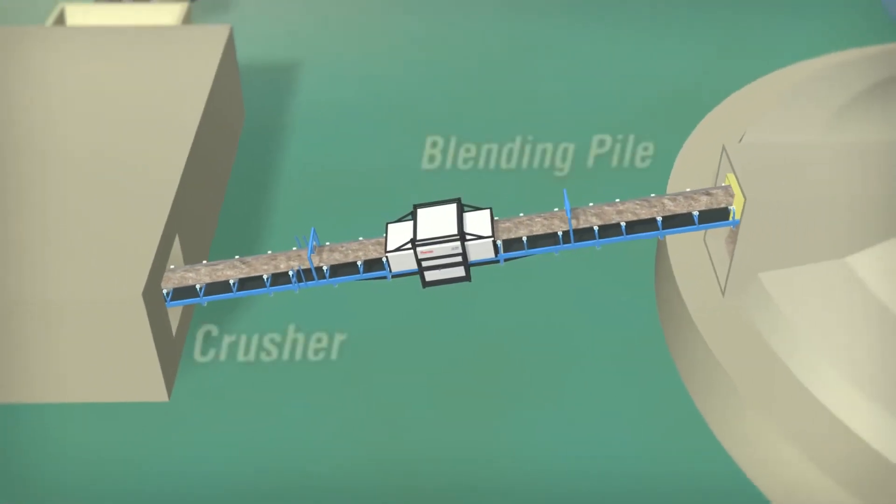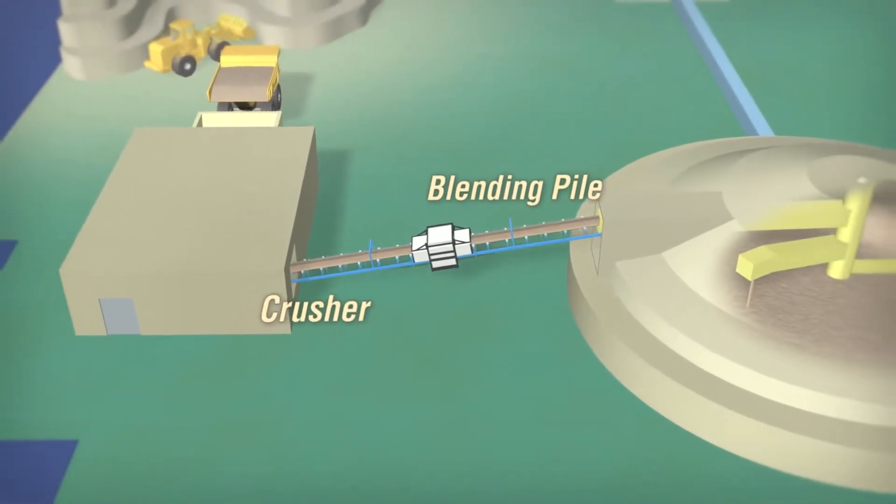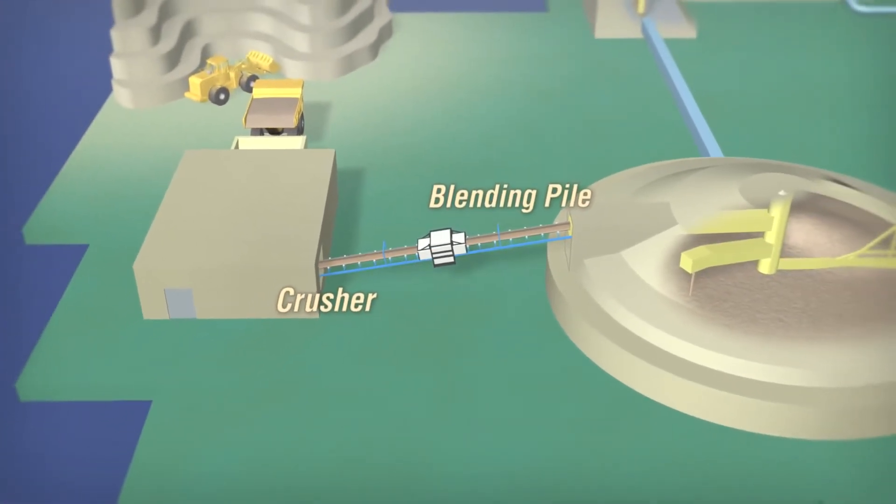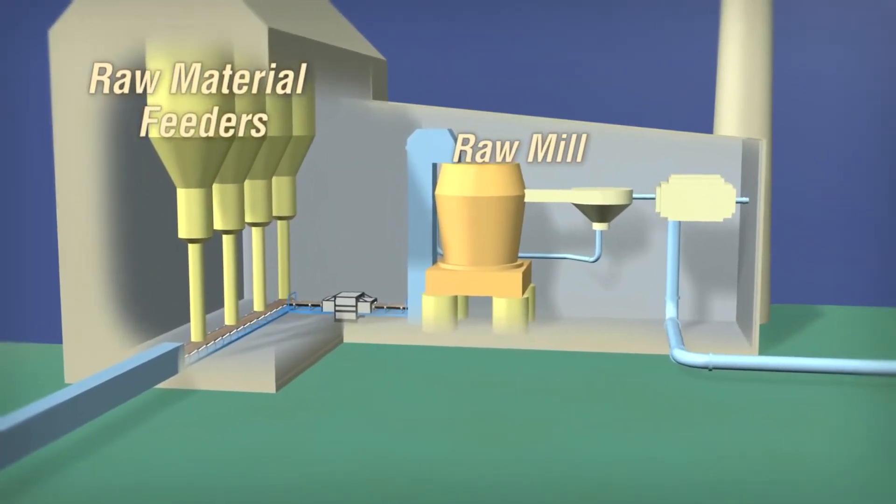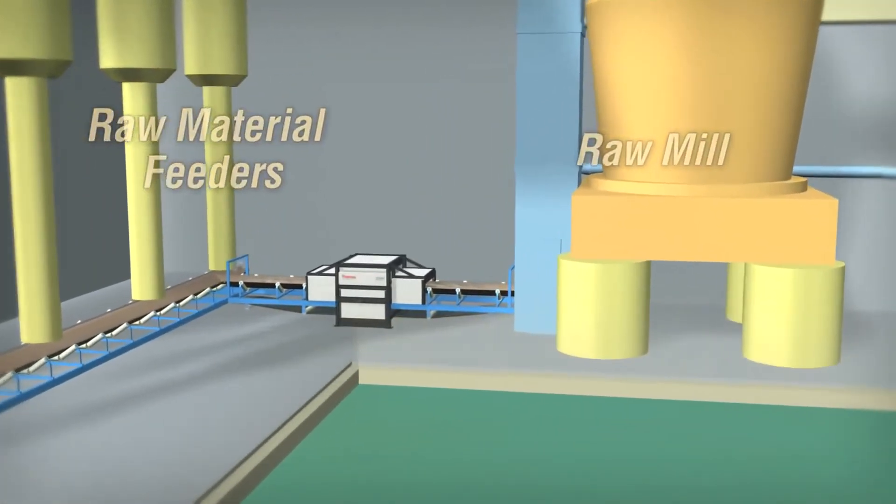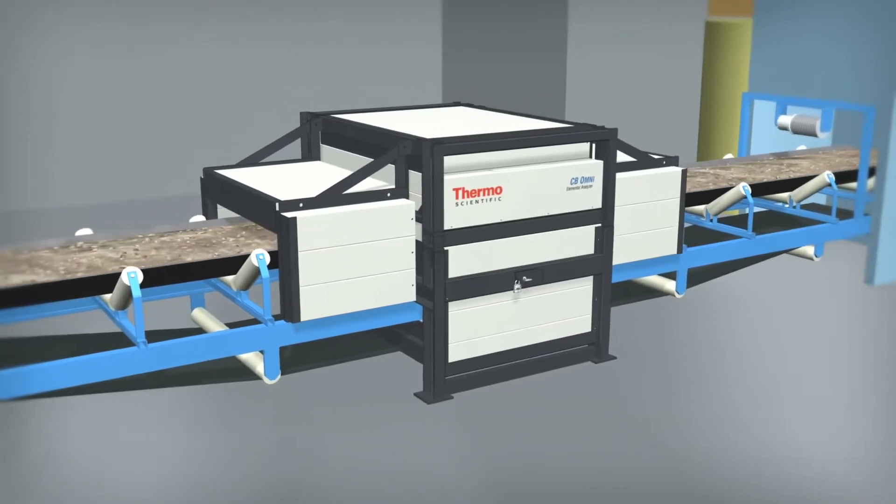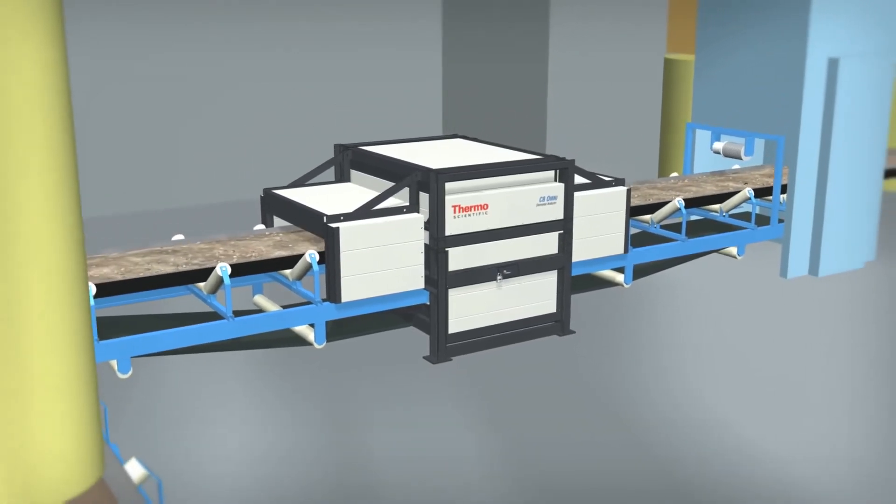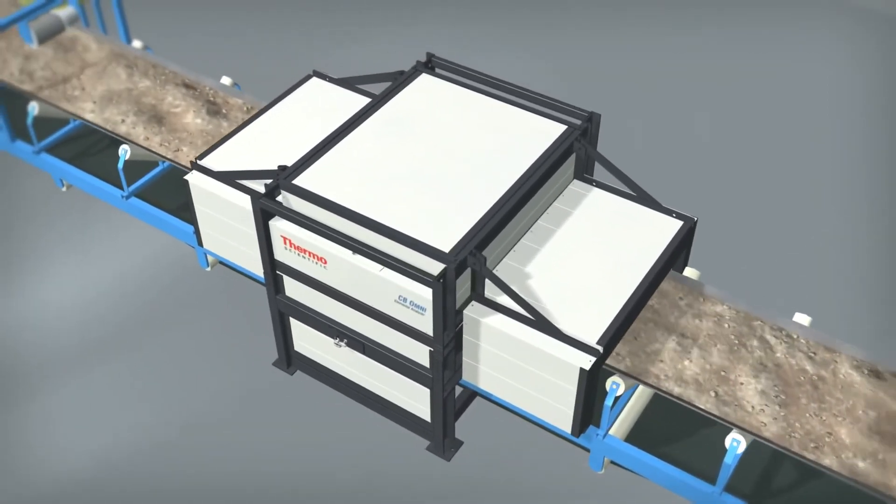In a stockpile blending application, the analyzer is located after the crusher but before the blending pile. In the raw mix proportioning area, the analyzer is located after the raw material feeders but before the raw mill. The system analyzes changes in raw material additives and responds rapidly by automatically adjusting the feed rates.